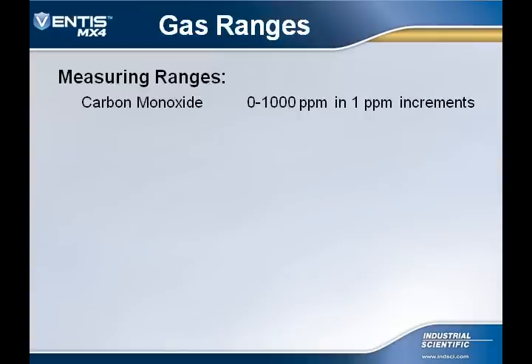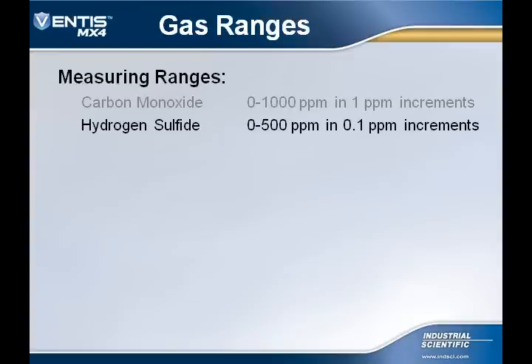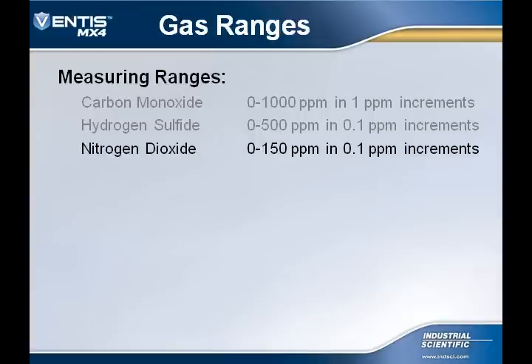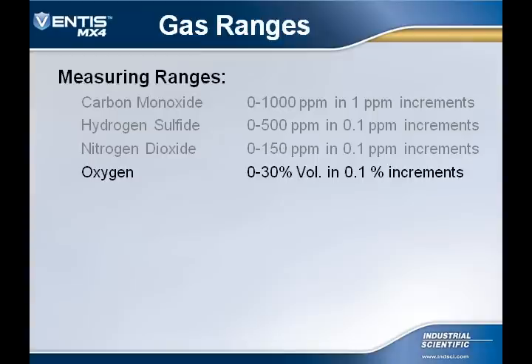The first sensor we'll take a look at is the carbon monoxide sensor. The measuring range is from 0 to 1000 ppm in 1 ppm increments. The hydrogen sulfide sensor has a measuring range from 0 to 500 ppm in 0.1 ppm increments. The nitrogen dioxide sensor has a measuring range from 0 to 150 ppm in 0.1 ppm increments. The oxygen sensor has a measuring range from 0 to 30% by volume and measures in 0.1% increments.